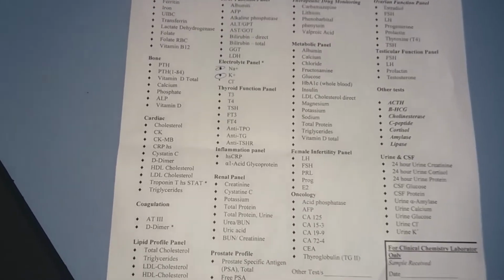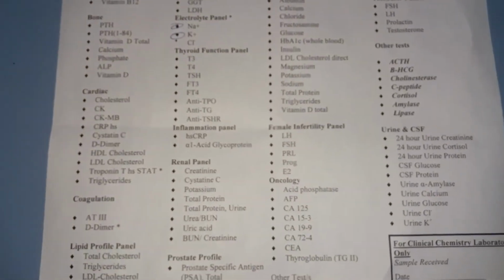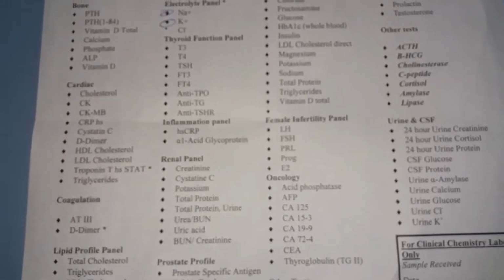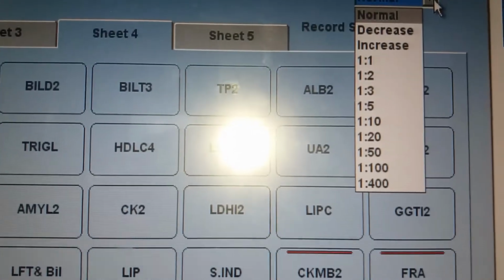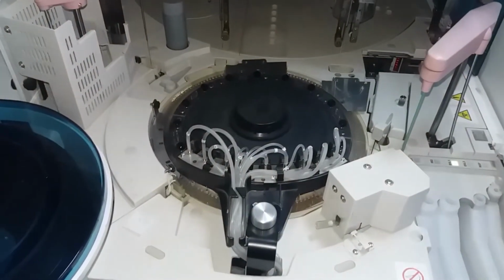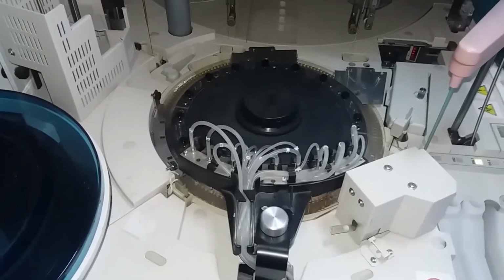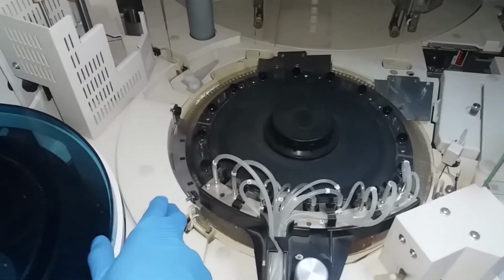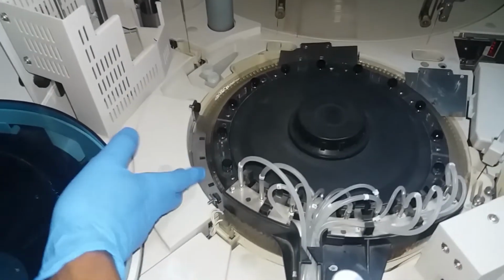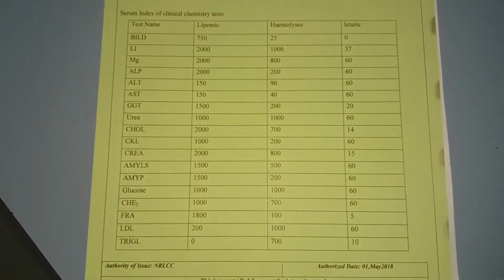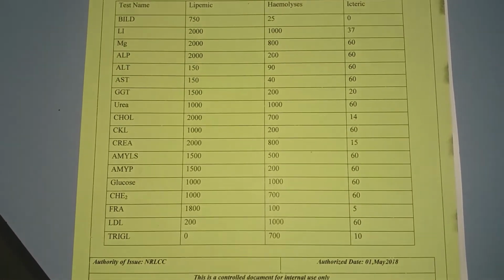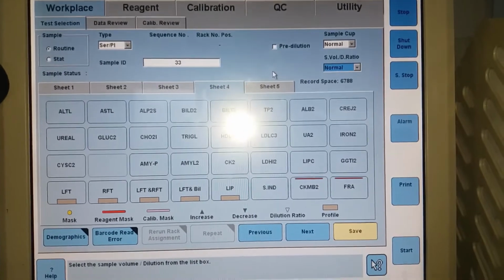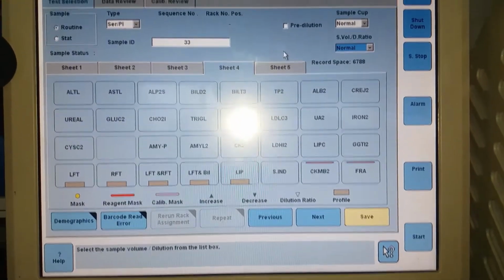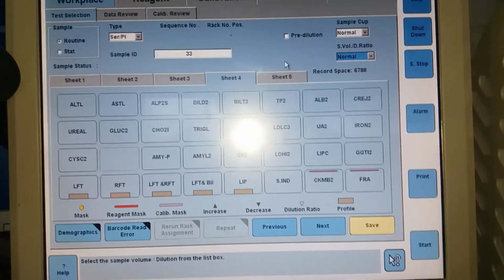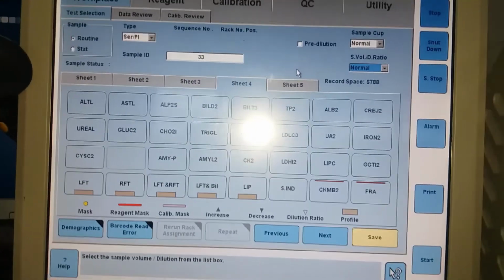There is an automated sample rerun and dilution mechanism found on this instrument. When we see the test integrity measures used in the Cobas 6000, there is a contact-free ultrasonic mixing station. There is determination of serum indices, those are tests for lipemic, hemolytic, and icteric samples. There is clot and liquid level detection on this instrument.